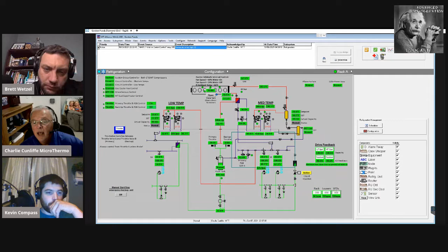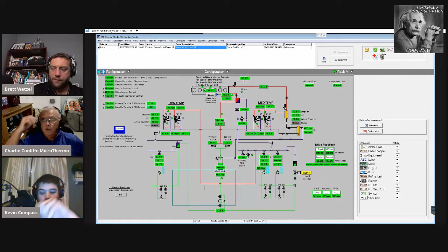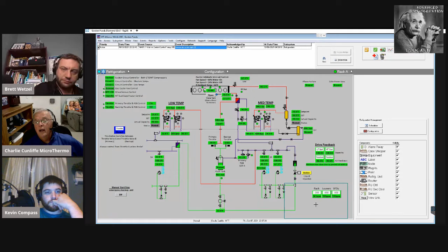You see here, they do actual liquid injection, and they do heat exchangers, so they add a couple extra bells and whistles, more than I've seen on other stores. That's probably why they did the jailbreak and have that MPC on the gas cooler control rather than something off the shelf. So it looks like what they did on the gas cooler here is they actually wrote a custom program for that.